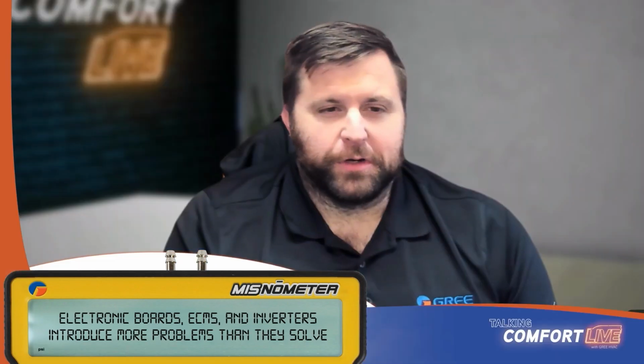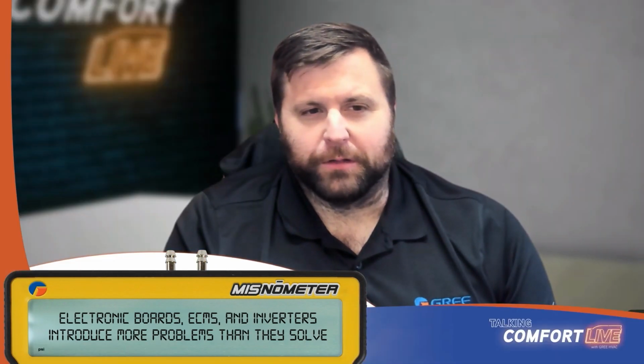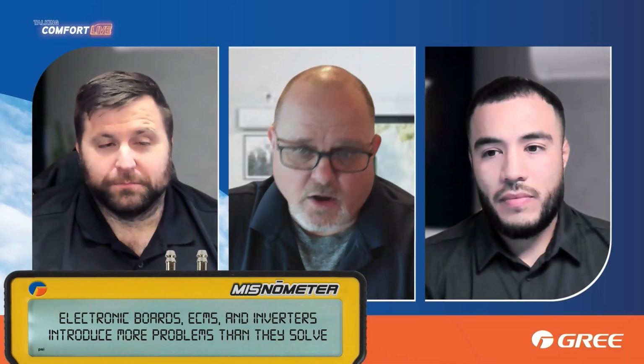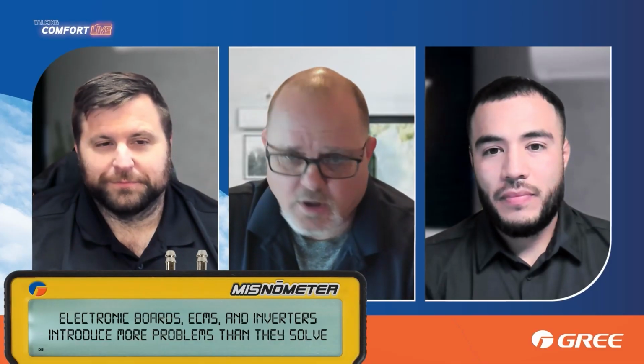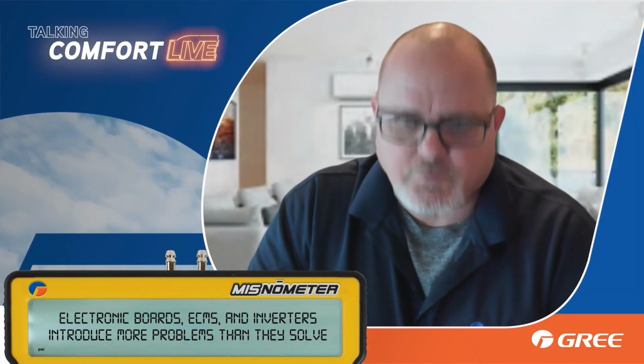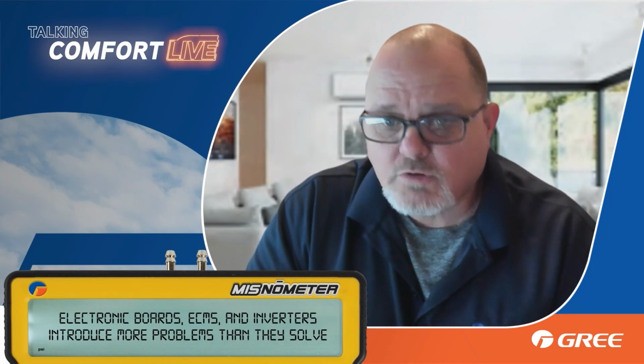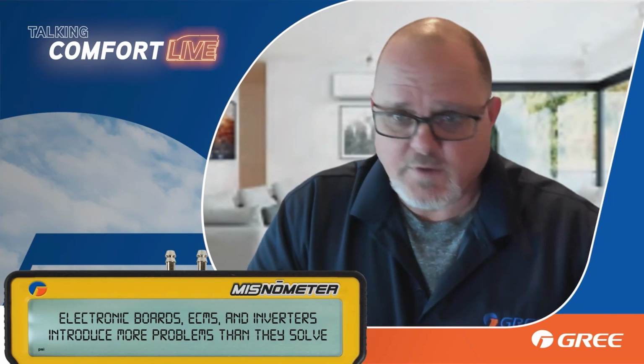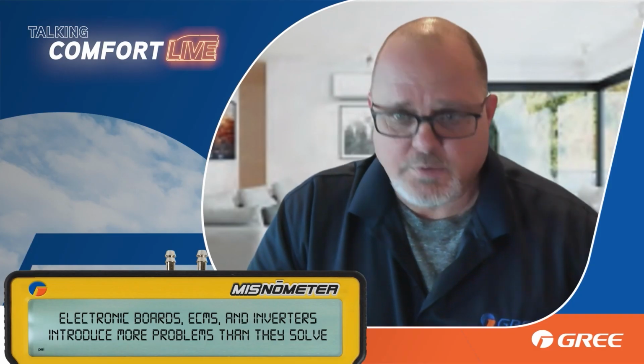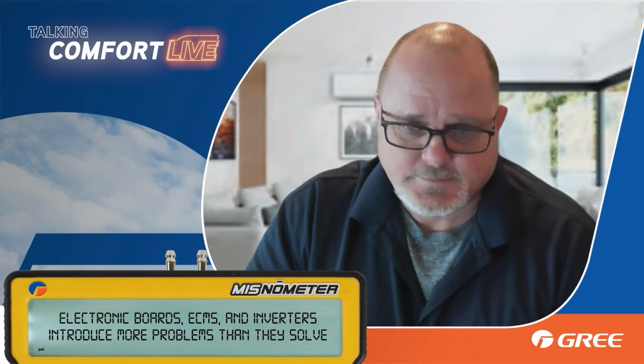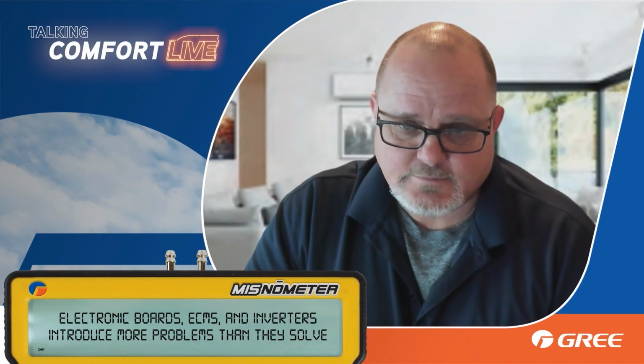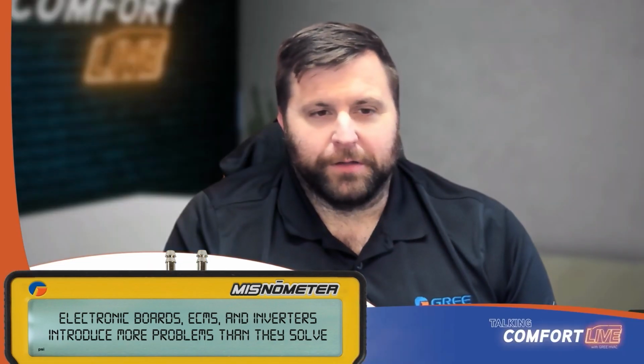Right. Well, crack open an ECM fan motor and you find out really quickly that it's just an inverter. It's a great example. If you take that end bell off of a variable speed blower motor, you've got a 3-wire Molex plug that plugs the ECM module to that motor. When you unplug that and ohm that out, you're ohming out a 3-phase AC motor, no different than a 3-phase AC motor in a mini split that's actually the compressor. Right. Yeah. Or if you work on a commercial rooftop, the 3-phase blower motor, it's no different motor-wise.